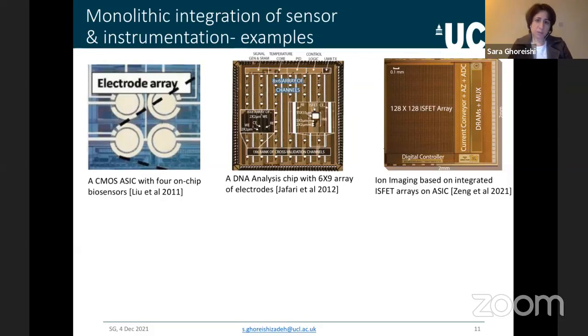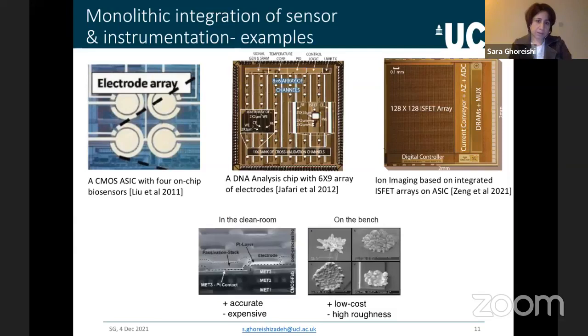So depending on what we want to measure and depending on the type of our sensor, our electrode may need to have a direct contact to the biofluid, to the gas, to the environment actually that we want to measure from. The ISFET array on the right really doesn't need a direct metallic contact to the biofluid and is covered with insulating materials. But the 2 examples on the left do need a direct contact, hence being covered with gold. And there are various methods we can cover these aluminum layers with gold or other inert metals.